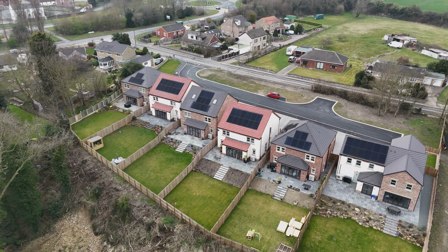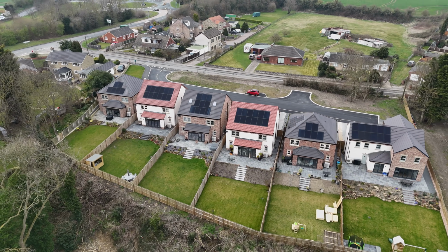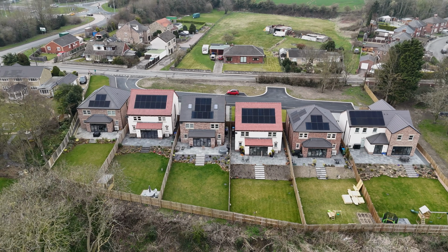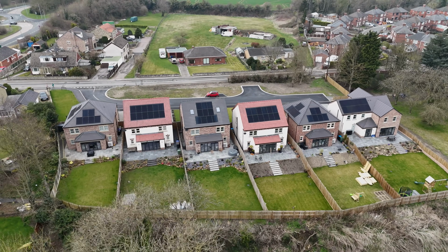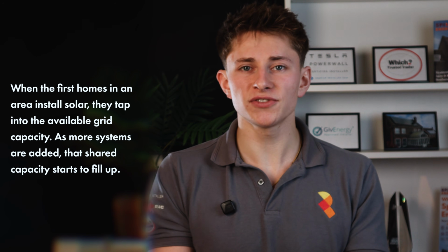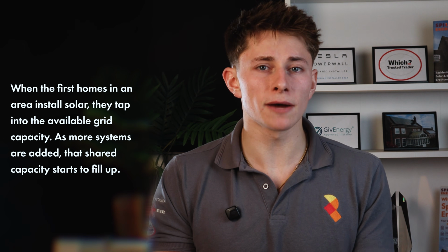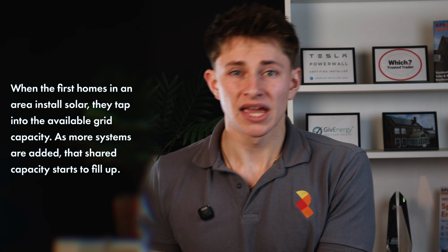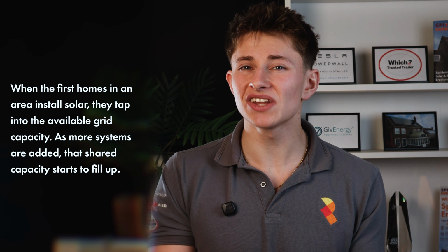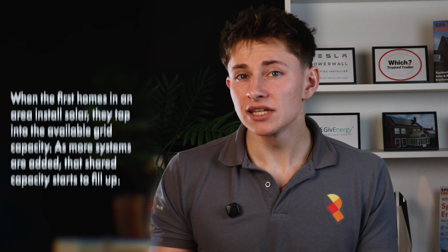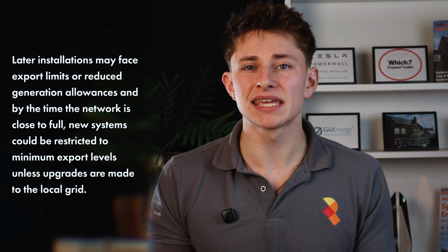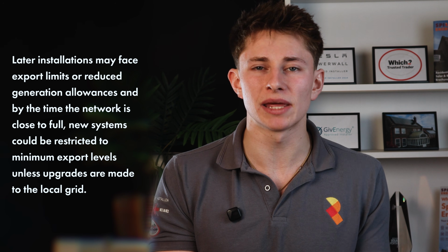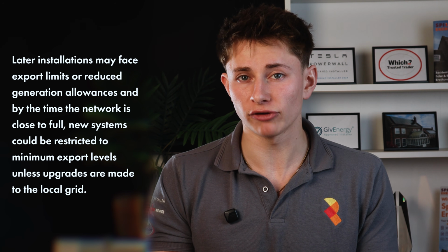Imagine a cul-de-sac with 10 houses fed by one cable from a transformer that branches off to each home. That local network has a limited amount of headroom for microgeneration, like solar PV and batteries, which are exporting to the grid. When the first few houses install solar, they use up some of that available capacity. As more houses add systems, there's less export headroom left, so the later homes may be given restrictions such as an export limit or reduced allowed generation.